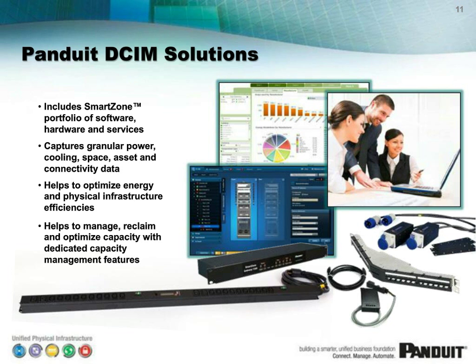Panduit also offers advisory services that can support SmartZone customers, design services, and on-site audit and assessment, such as thermal assessment services that can identify and address hotspots and cooling issues while providing valuable cooling capacity information, helping to future-proof data centers against development of further thermal problems. So our assessment services, our optimization services, take advantage of the actionable intelligence and provide the customer with actions that can be done to reclaim some of the identified stranded capacity.